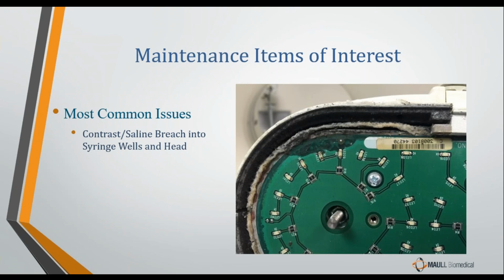Now, some of the most common issues. One of the biggest issues by far that's going to be a headache for you and have you called down to take a look at it is fluid breaches into the injector head. When the operators are filling the syringes up, they tend to spill contrast. Sometimes they can spill a lot of contrast. And when contrast gets down inside the head, it can wreak havoc, obviously.